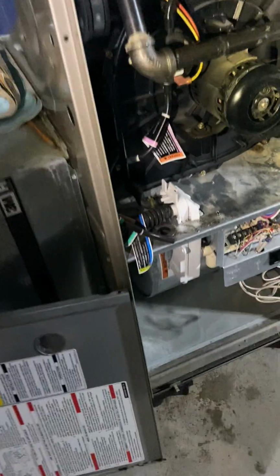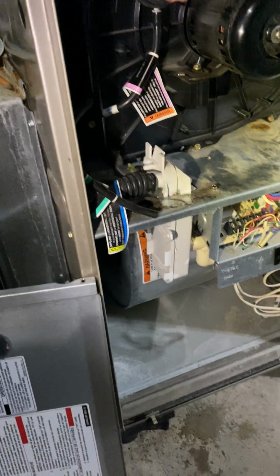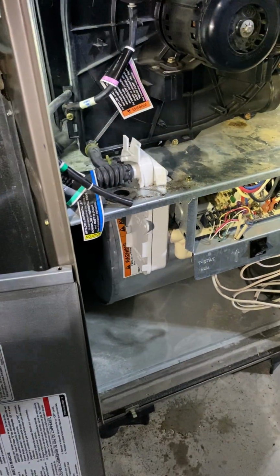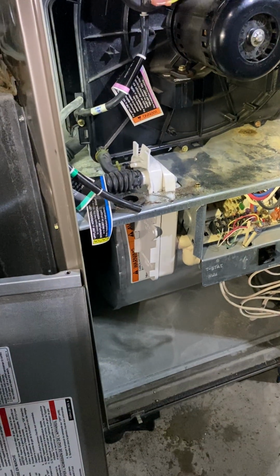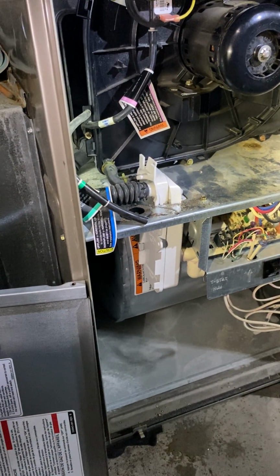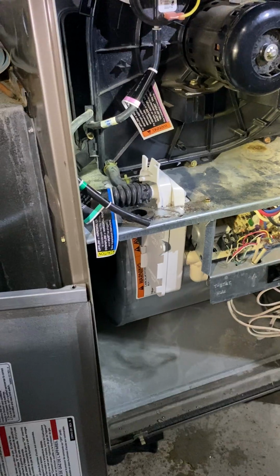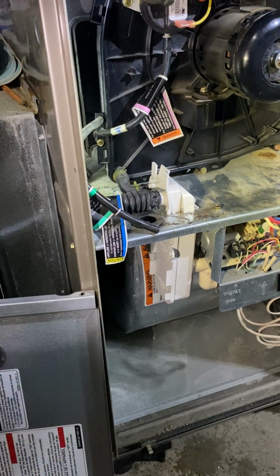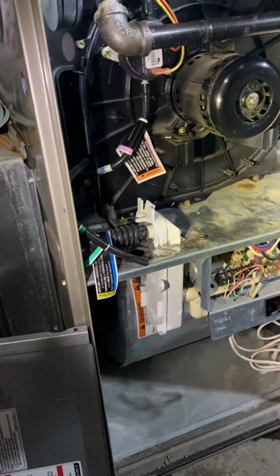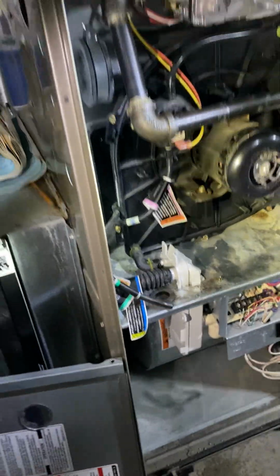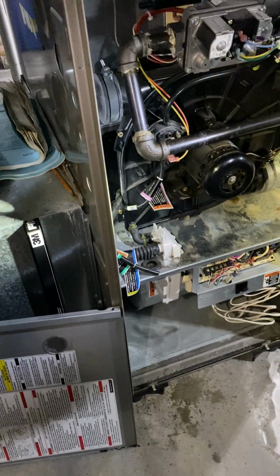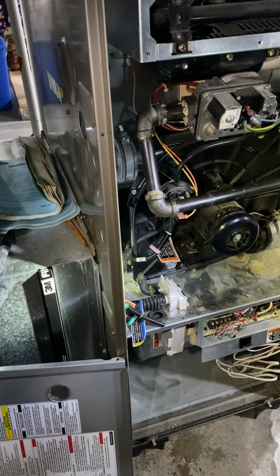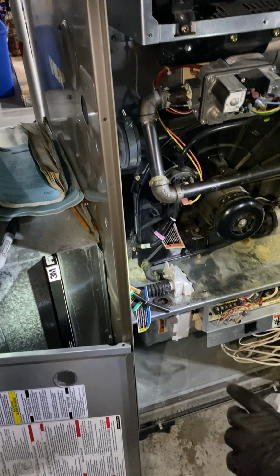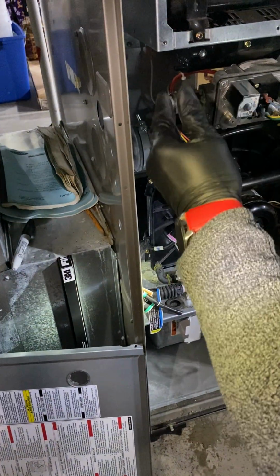This furnace, we're gonna do a combustion test on here too. These older high efficiency carriers, 12 to 15 years old, always do a combustion test, because the heat exchangers fail on these. It's not really the heat exchanger or the carrier, it's because they're installed wrong. Just like I always tell our lead installer Mike, high efficiency furnaces should be installed with a pitch.